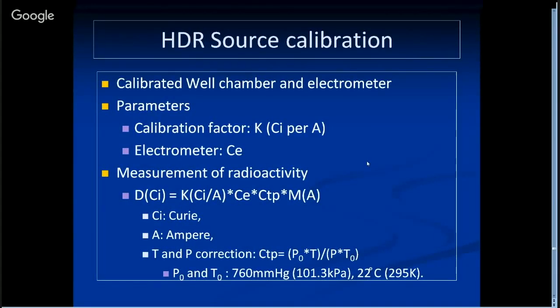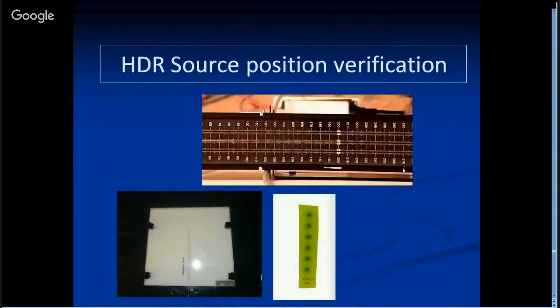For source calibration, you need a calibrated well chamber and calibrated electrometer, and you need to know the calibration factor for the electrometer. With that, you measure the data M in amps, apply the calibration factor K and the temperature and pressure correction factor, and you get the source activity. You also need to verify the source position.